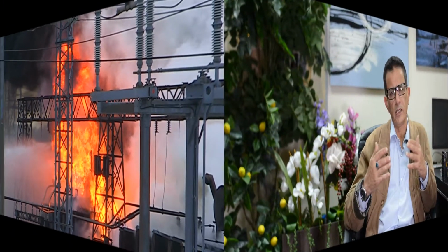Our transformer is not, as we said, designed, built or operated to be a pressurized vessel. It's only supposed to withstand small overpressure. And in case of high pressure, due to abnormal operation or fault conditions, there should be a way to protect the transformer from explosion. Explosion of a transformer is very dangerous. It can affect humans, animals, the environment, assets, everything. There are many ways to protect the transformer. For power transformers, there are many sophisticated aids and tools, like the Buchholz relay and other things. But for our oil-filled distribution transformer, the most popular thing is to use the pressure relief valve.